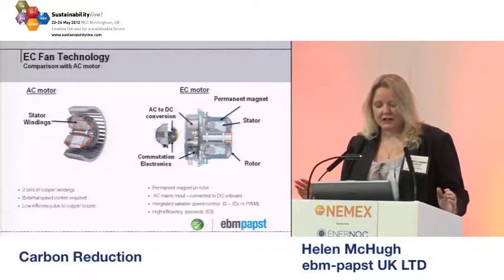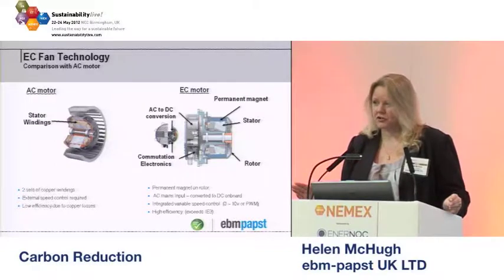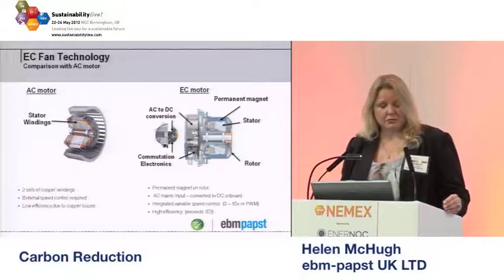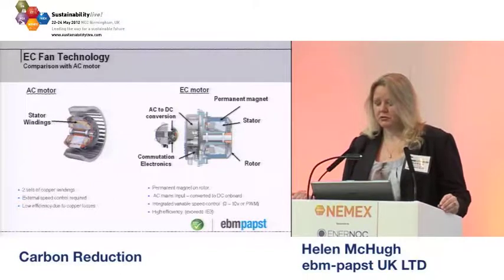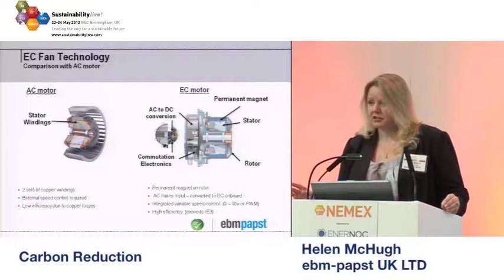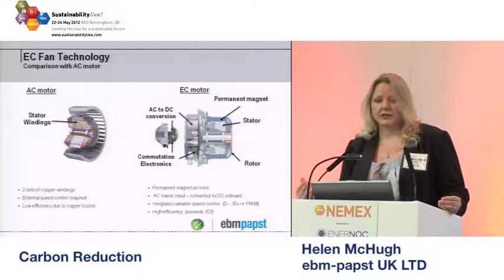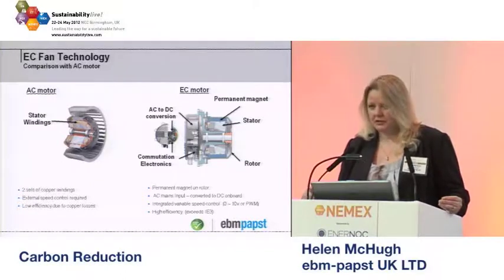So basically you've got a highly efficient motor. It's a DC motor. But what is so important about this is that it's got onboard electronics, so that the motor, it's an AC input which converts to DC on board, and within those electronics we also incorporate all the speed control. So traditionally for an AC motor you would have added a variable speed drive, an inverter control. You don't need to do that because that's all integrated into the electronics.